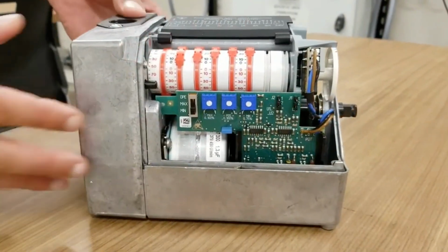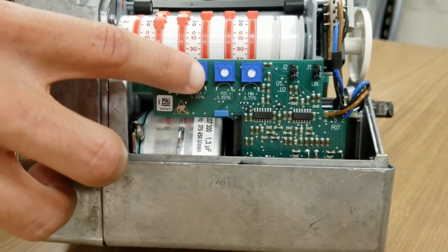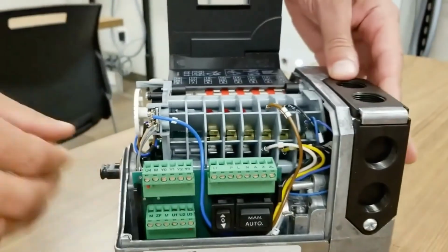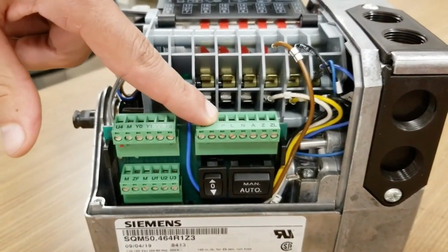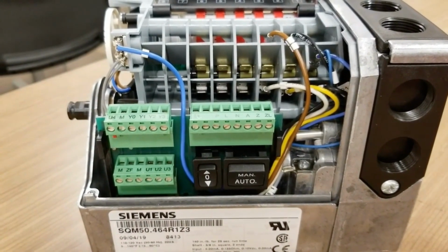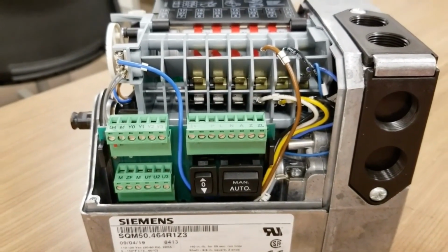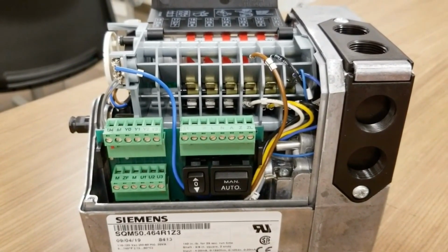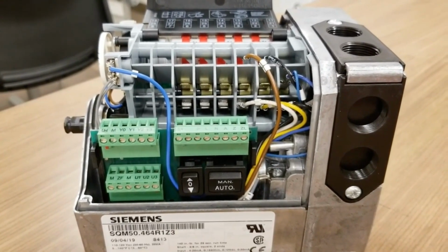In addition to the min and max pots, you'll also notice this POS pot on the back of the actuator. This corresponds to the P input terminal on the front of the actuator. If you supply line voltage to this P terminal, all analog input signals will be overwritten and the actuator will move to a position set by the POS potentiometer. This position can be set to any spot within the actuator's range of operation defined by switches 1 and 2.